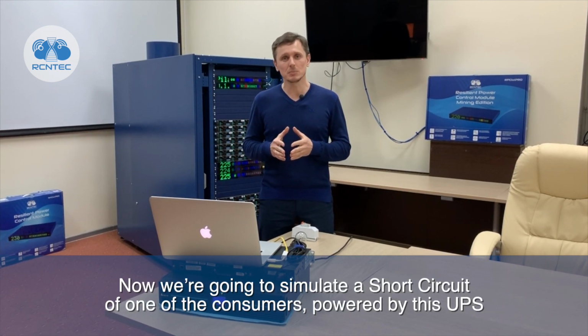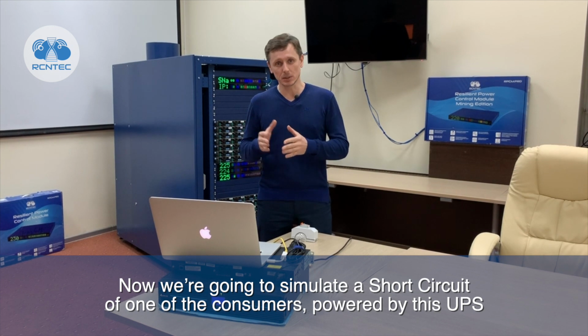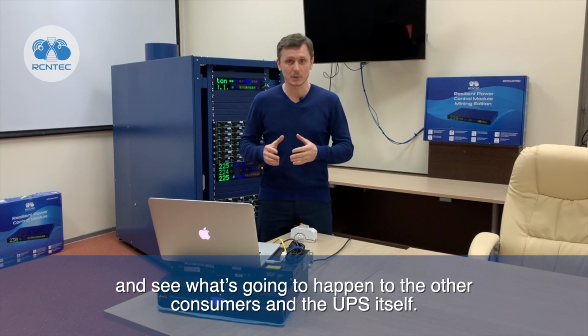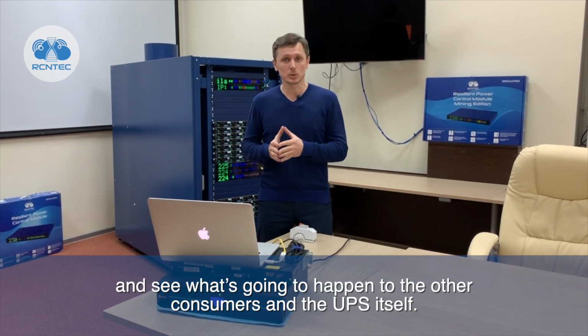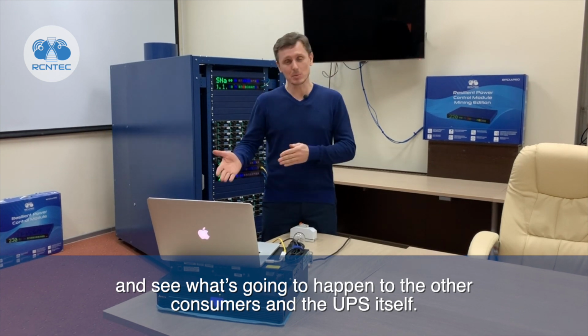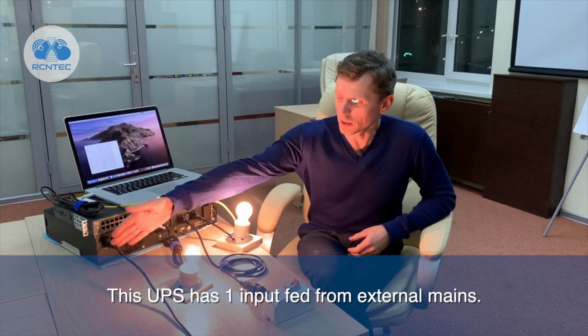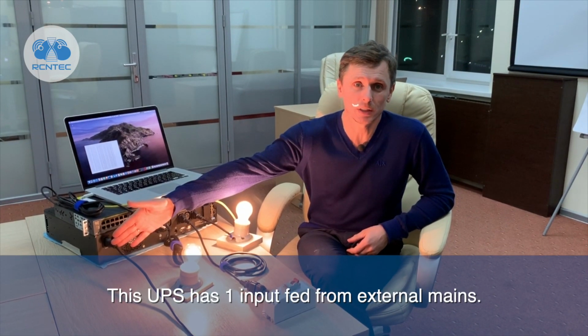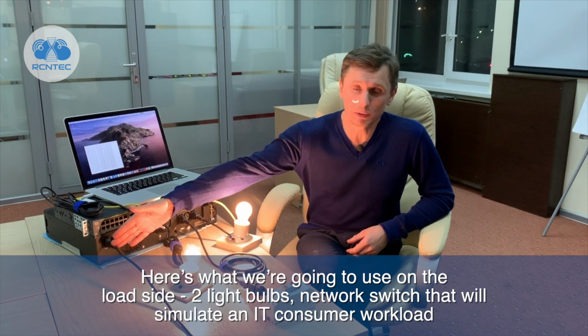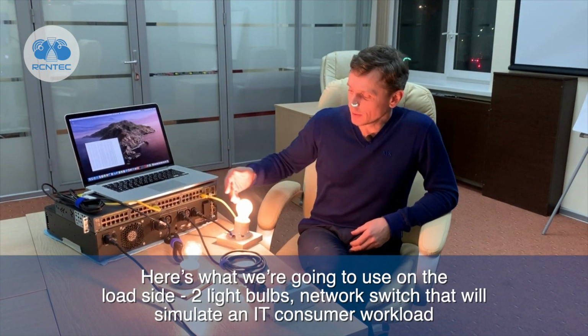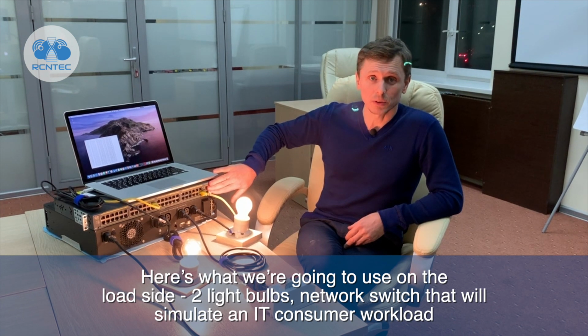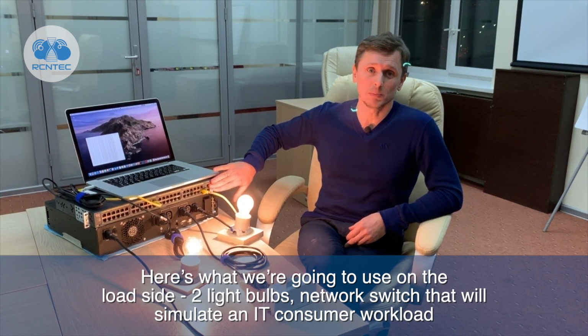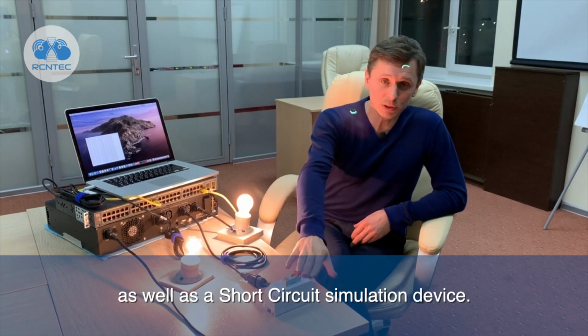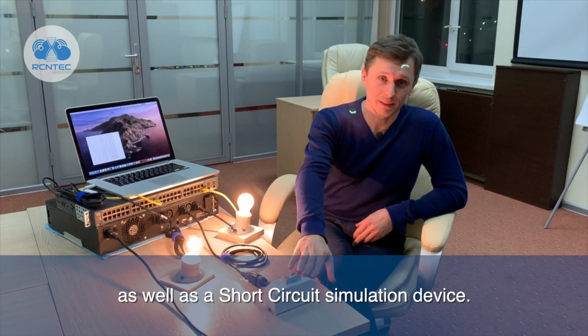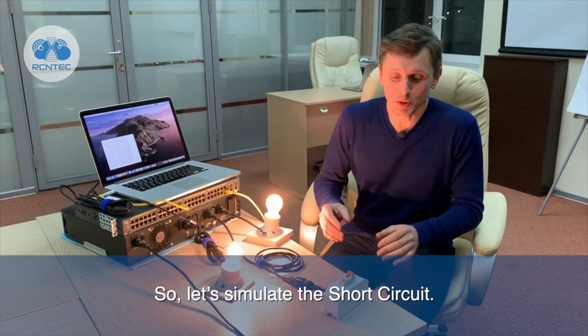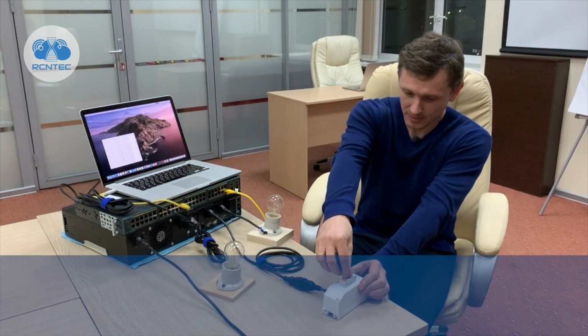Now we're going to simulate a short circuit of one of the consumers powered by this UPS and see what's going to happen to the other consumers and the UPS itself. This UPS has one input fed from external mains. Here's what we're going to use on the load side: two light bulbs, a network switch that will simulate an IT consumer workload, as well as a short circuit simulation device. So let's simulate the short circuit.